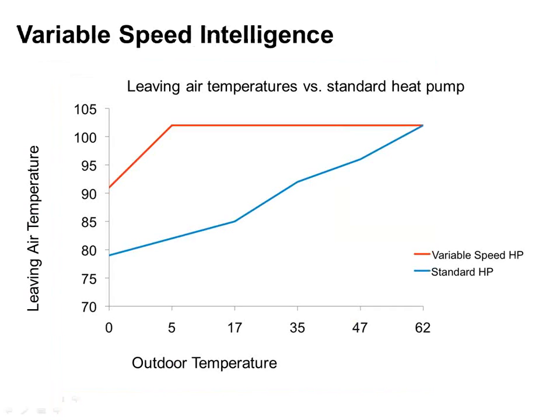If I were to graph it out like I have here, let me see if I can use my little red dot again. I hope you guys can see that little red dot. If I were to graph this out, a standard heat pump, which is in blue on here, I have outdoor temperature on the bottom and discharge air up the left-hand side. At 60 degrees out, or 62 in this case, I'm starting out with 102 degree air, which is great. That's perfect for me to heat a space. As it gets cooler outside, that air temperature starts dropping off, dropping off, dropping off. By the time I get down to 35 degrees, I have 90 degree discharge air. When I'm down at 17, I have 84 degree discharge air, and people are going to bitch.